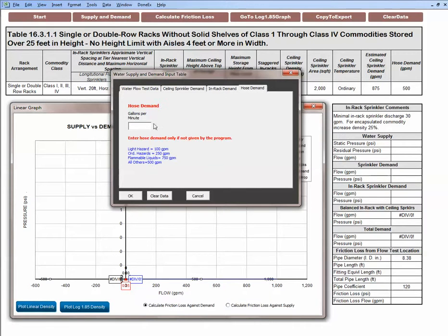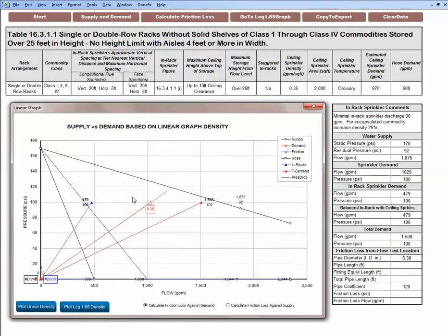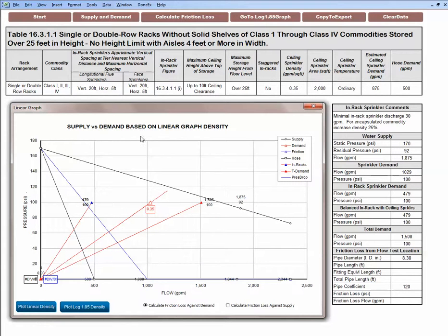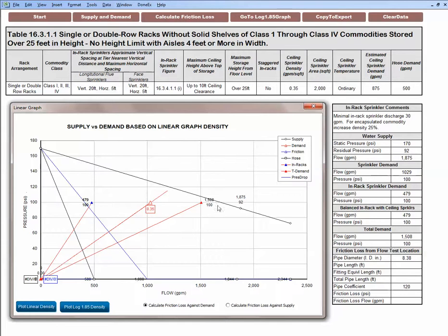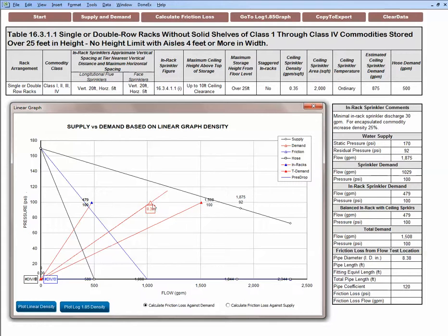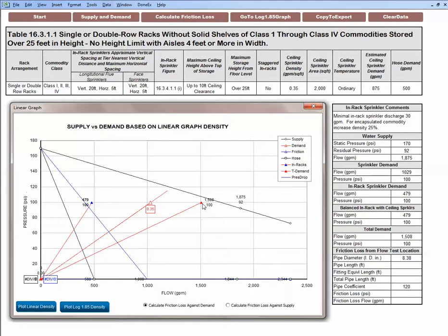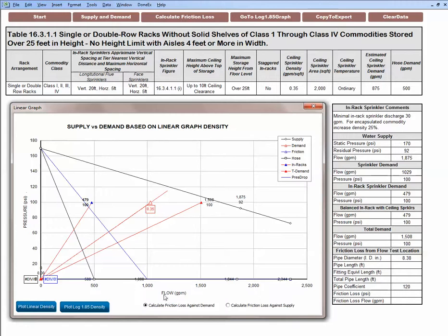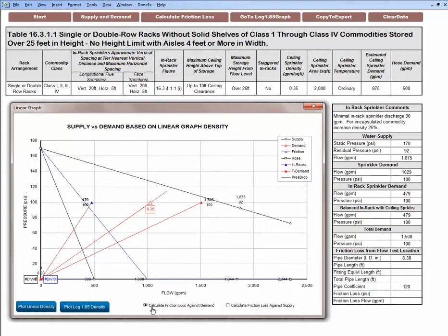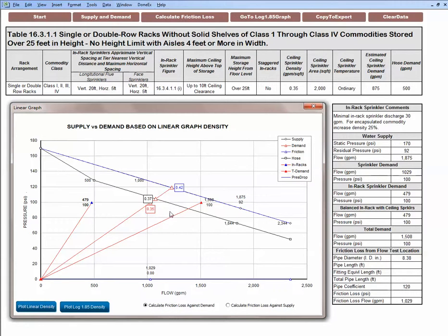We'll enter hose demand but hose demand is already given so I'll leave this blank. I'm accepting 500 gallons per minute. We click OK. And when we do, the computer calculates and enters the water supply, in-rack sprinkler demand, and ceiling sprinkler demand. The density needed is 0.35 and it calculated your total demand for ceiling and in-rack sprinklers. The lines look a little bit funny but this is because the program calculated friction loss also to the base of riser. So I'm going to click this button calculate friction loss against demand and the line straightens there now.